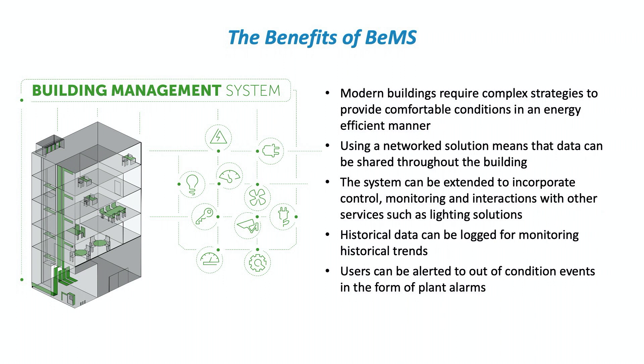With a network solution we can share data throughout the building. Using fast communications, a BEMS can look at the position of every single valve in a building and establish what the demand is for the boilers or chillers, creating quite complicated control strategies. The system can also be extended to incorporate monitoring interactions with other services — for example, a lighting occupancy sensor that detects someone entering a room can feed that information into the BEMS to affect heating or cooling as well.